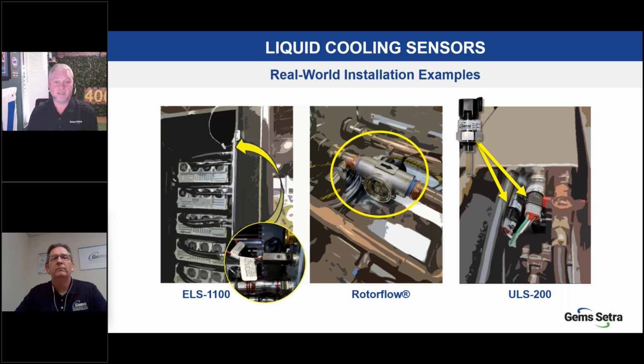You see on the left here the ELS 1100 used at a top of the manifold with a tight tolerance of available space, where that ELS 1100's small footprint and the sensing prism is extremely beneficial. The Rotorflow in the middle here is used in a rack-based CDU to monitor continuous flow with the analog output signal in a redundant pump loop.